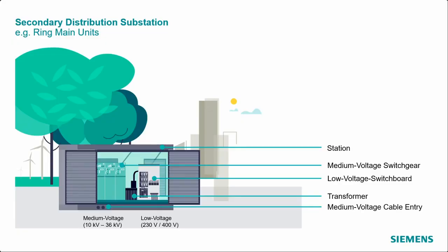Now let's go closer to the end consumers. This is a secondary distribution substation, which is a facility that steps down the medium voltage coming from the main substation to low voltage for final consumption. These types of substations are typically located close to the end consumers. Some of the main components of the secondary distribution substations are medium voltage cable entry for the energy coming from the power grid, one medium voltage switchgear to receive this power, one transformer to step down this medium voltage to low voltage, and one low voltage switchboard to deliver this low voltage to final residential consumption.